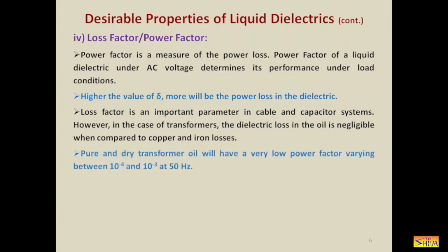Pure and dry transformer oil will have a very low power factor, varying between 10 to the power minus 4 and 10 to the power minus 3 at 50 Hertz. Here, the mention of frequency is important, because there is a capacitive component and it is frequency dependent. Therefore, whenever we specify the power factor or loss factor for AC application, we mention the frequency. In general, our frequency is 50 Hertz, therefore it is mentioned.